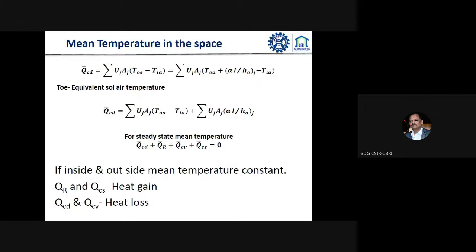with respect to conduction, the simplified equation, that is UA. U is given because the different layers are given. So UA, the external minus internal, with this we can find out this particular heat gain. So here, in case of the opaque body, apart from your normal temperature gain through the surface, there is also the solar excess temperature that is involved. So that is the additional factor that we need to consider, so that we can get the total heat gain.